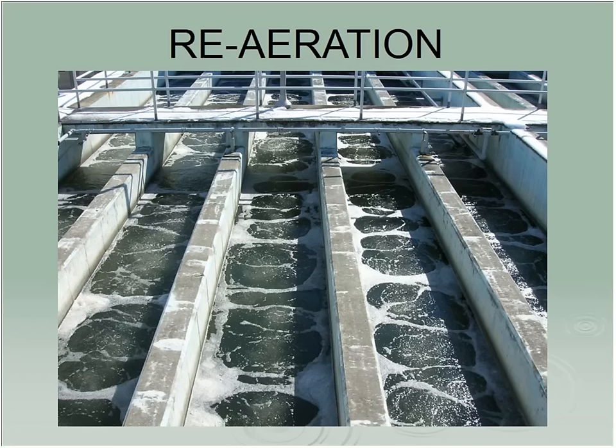So BOD's down, suspended solids down, maybe our nutrients are down where they should be. We've got nice clean water. We've killed off the pathogens, at least to a point where we're happy. One final thing to do before we let this go. The last time this water saw any air was back in our biological process. We have to pump a lot of air in there to keep the bugs happy. So it went through a clarifier, which is probably 2 to 3 hours. It went through a contact tank, which is a half an hour. So there's still a little bit of food, a little bit of bugs, and no oxygen. So what we have to do is re-aerate.